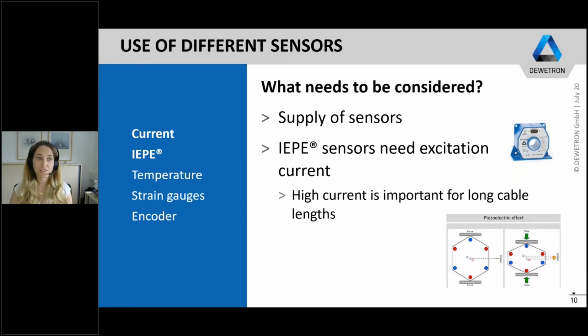For IEPE sensors, so acceleration sensors, also the excitation current is very important. These sensors are based on a piezoelectric effect where a force causes a displacement of the charges and a voltage can be measured, as you can see in the picture below. The excitation current is also used for the internal electronics, which consumes up to about 1 milliampere. And typical excitation currents for those sensors are 4 or 8 milliampere.